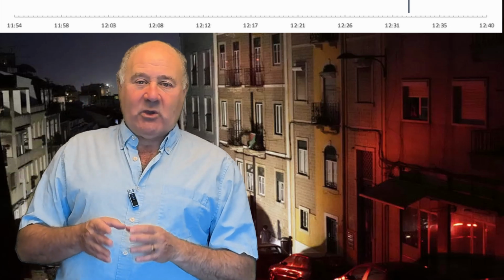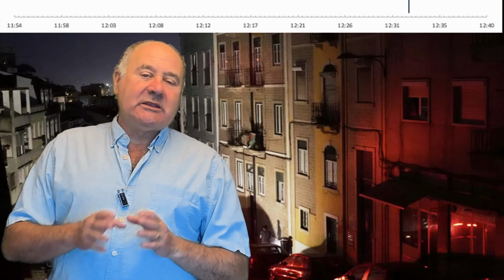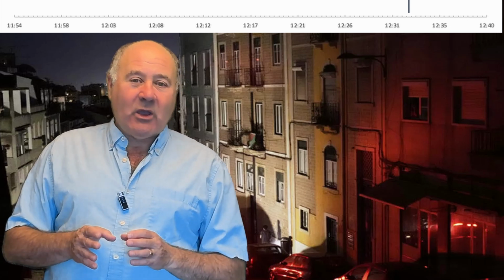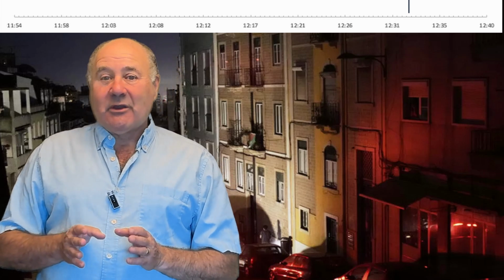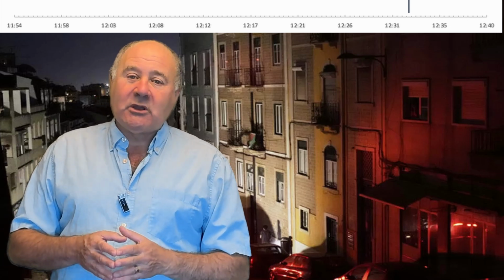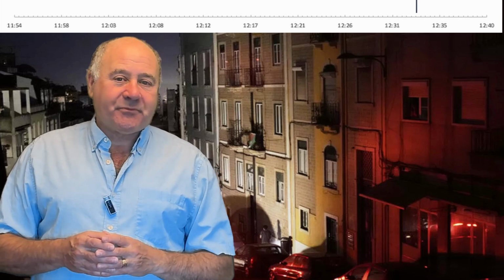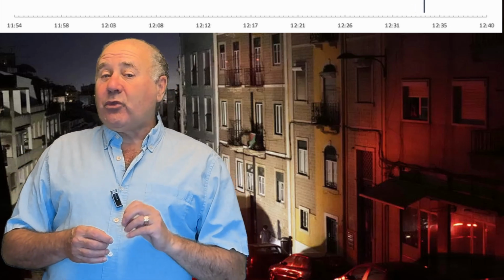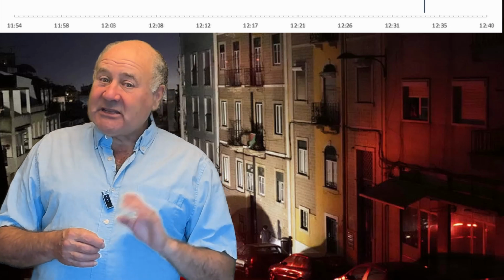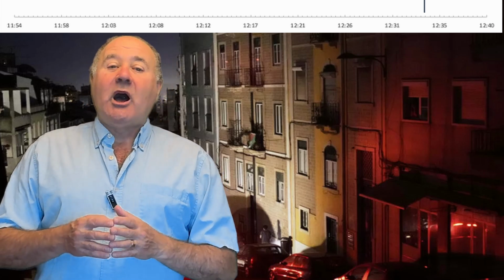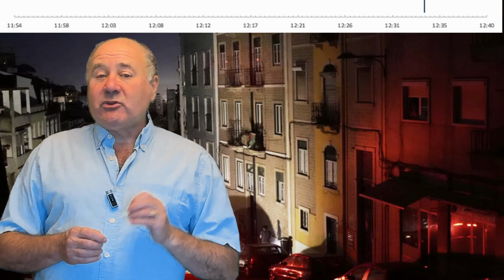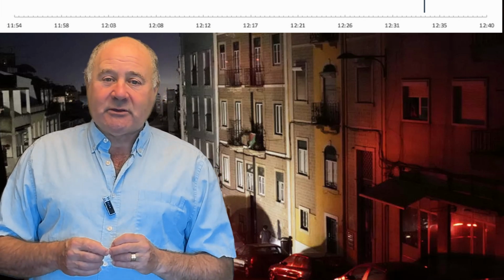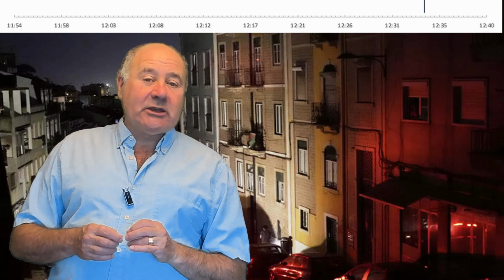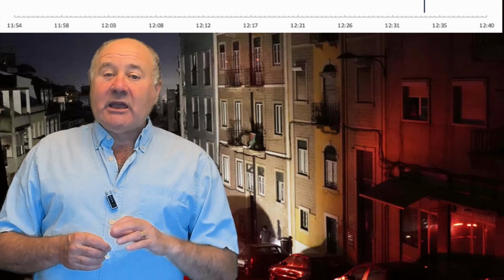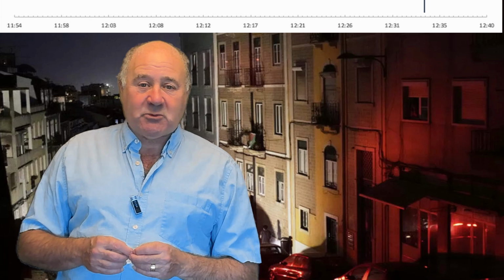Management of reactive power is now an issue. I'm not going to go into the details of reactive versus active power, as it's complicated and not intuitive. But in brief, reactive power is important for inductive loads like motors and is critical to managing the grid. At 12:33 and 16 seconds, 19 seconds after the trip in Granada, another line tripped, taking 582 megawatts of production with it. 360 milliseconds later, a solar power plant went offline, taking an additional 145 megawatts with it.